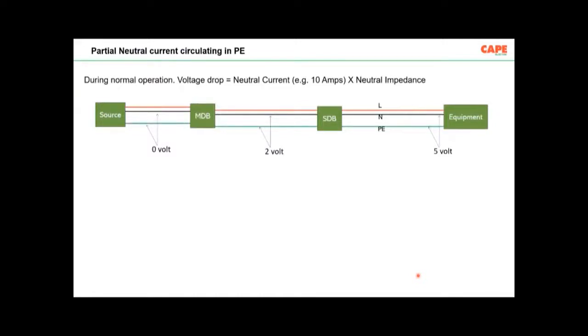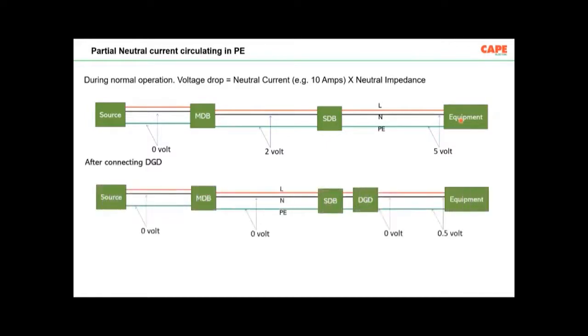This being the fact, practically what do we do? I'm just showing you a classic example. There is a source, let us say in an IT building. The neutral is earthed. The potential between neutral and earth closer to the source is near to 0 volt. After the MDB, probably the neutral and earth is 2 volt. Near to the equipment, the voltage between neutral and earth is sometimes 5 volt. The equipment vendor, if it is a sensitive equipment, always says that my equipment will fail if the voltage is 5 volt. So they always demand a voltage of less than, for example, 1 volt. Otherwise, your equipment will fail.